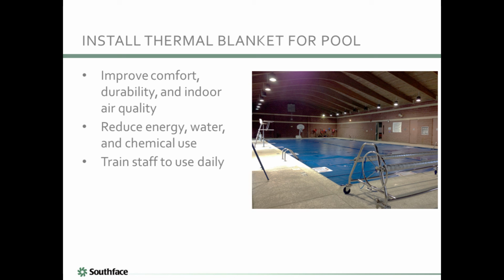Pool covers are required by the Energy Code, ASHRAE 90.1. The energy and water and cost savings are huge. However, a study by USA Swimming estimates that only 5% of natatoriums use the thermal blanket. So this issue is pretty widespread. The best way to reap the energy savings from installing a thermal blanket is to purchase a retractable thermal blanket that can be wound onto a storage reel. This type of pool cover is designed to be deployed and retracted quickly on a daily basis. This pool cover can be rolled onto the spool and stored in a convenient location.